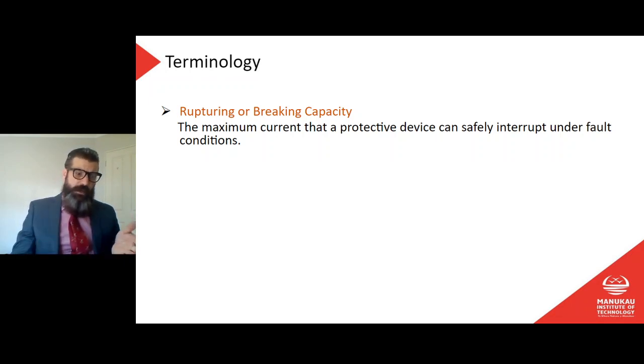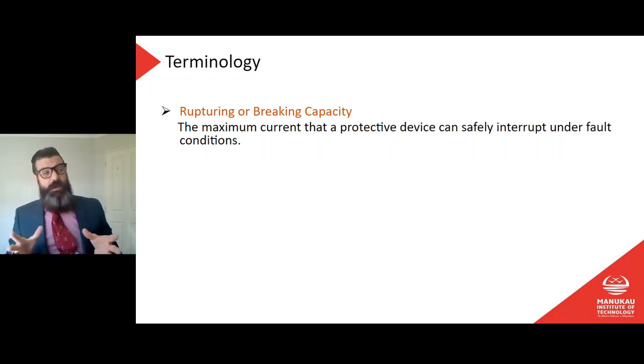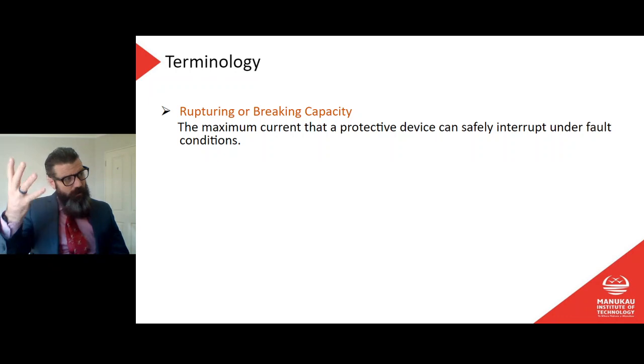So when we measure our short circuit current or our earth loop impedance, what we're doing there is trying to work out what's the highest current that will flow in the circuit if I make a short circuit here, and will my circuit breakers still operate correctly in that condition. Now, most of the time what we've found when we've done earth loop impedance testing and prospective short circuit current testing is that our prospective short circuit currents in P block on the fourth floor are something like 400 to 500 amps. And the typical breaking capacity of the circuit breakers installed in there is something around 6,000, and that's pretty standard. 6,000 is pretty normal.